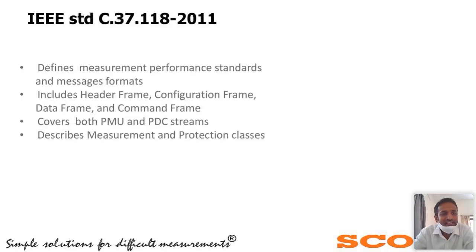And this is what the IEEE standard defines: how to send this PMU data to the PDC. This particular protocol is called C37.118. There are many editions, like 2005, 2011, now 2014, and 2019 also coming up. Different editions have different advantages or additions of futuristic applications.